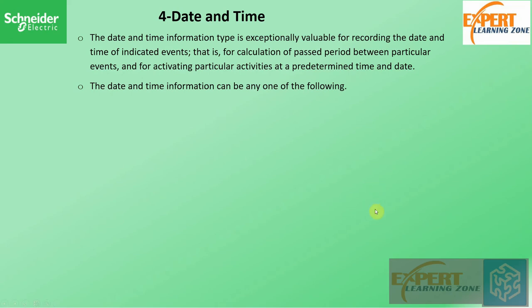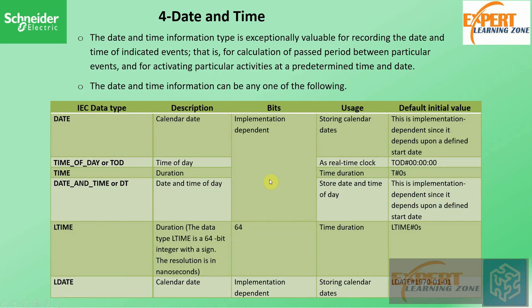Date and time information can be any one of the following. This table summarizes the types with their IEC type names. The DATE type is used to represent calendar dates; the number of bits is implementation dependent, and it stores calendar days. The default value is also implementation dependent — you can check the manual or documentation.